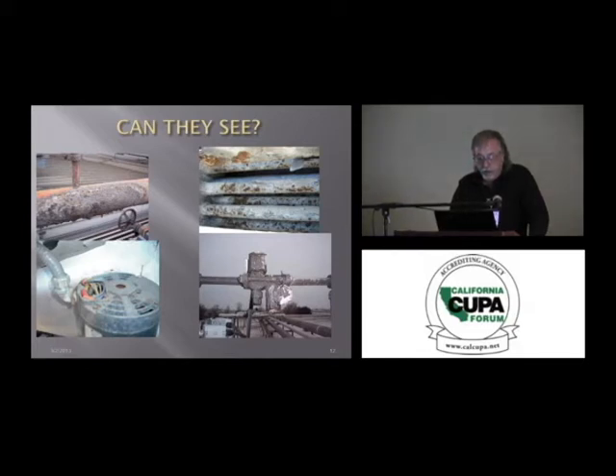On the left-hand side here, you've got a new galvanized coupon. We put these in condensers when we start our condensers up, because these coupons will show us the white rust before the condenser actually does. The center one is a coupon that's been attacked by white rust. Now, this is very aggressive here. Typically when it starts off, it just looks like a snowflake or two, and then it accelerates. And then the one on the right has been passivated with a protective coating to hold that zinc in. Otherwise, if you look up here at the right-hand side, this condenser right here was only 12 years old, maybe 14, 12 or 14 years old, and it's completely rusted.